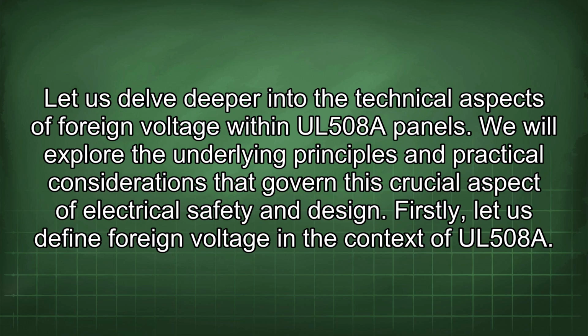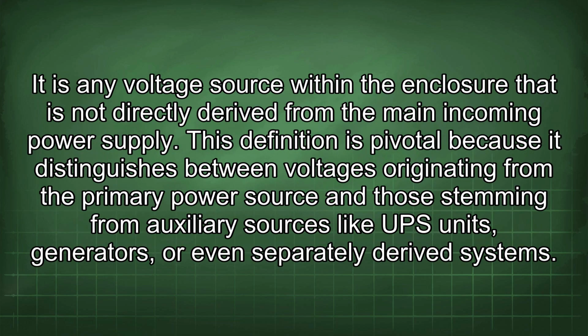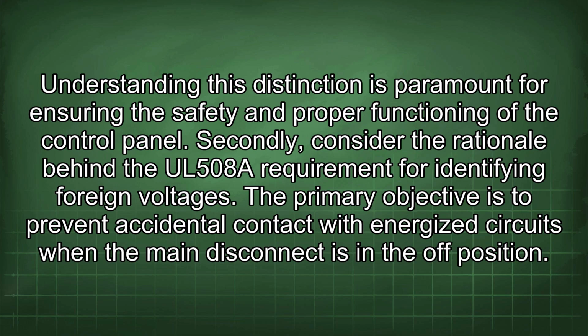Firstly, let us define foreign voltage in the context of UL508A. It is any voltage source within the enclosure that is not directly derived from the main incoming power supply. This definition is pivotal because it distinguishes between voltages originating from the primary power source and those stemming from auxiliary sources like UPS units, generators, or even separately derived systems. Understanding this distinction is paramount for ensuring the safety and proper functioning of the control panel.